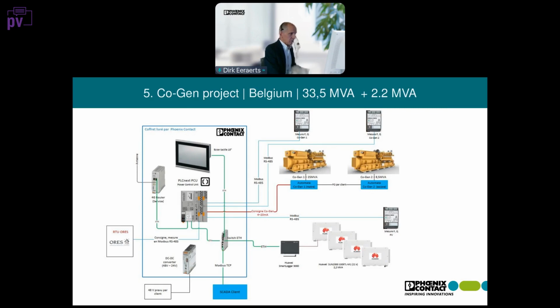Another and last example is a plant where we have 2 different types of generators. So here we have 2 cogeneration units and we have PV. Again, we have the same DSO ORES, but here you see that the commands are sent by Modbus RS485. And we communicate with the cogen over just analog signals. With the inverters, we do it through Ethernet SunSpec.